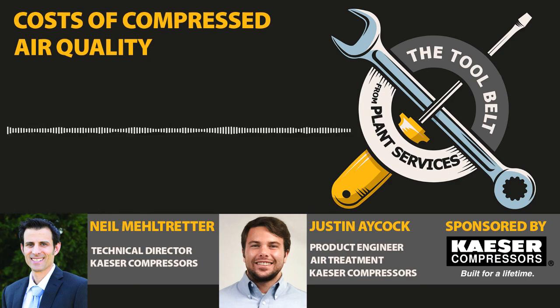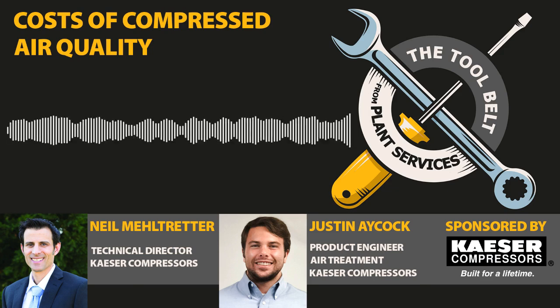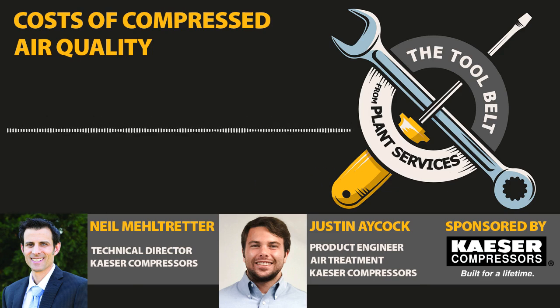So that would give you the best air quality with the most equipment, so it would obviously be the most expensive. If you had less stringent requirements, you would use less equipment or just different equipment, like a refrigerated dryer instead of a desiccant dryer, and that would definitely be a lot cheaper. So determining your ISO classes can help you choose the correct equipment and reduce your cost. Okay, those are great points. I'm curious, Neil, do you have specific application examples that you can share with us?